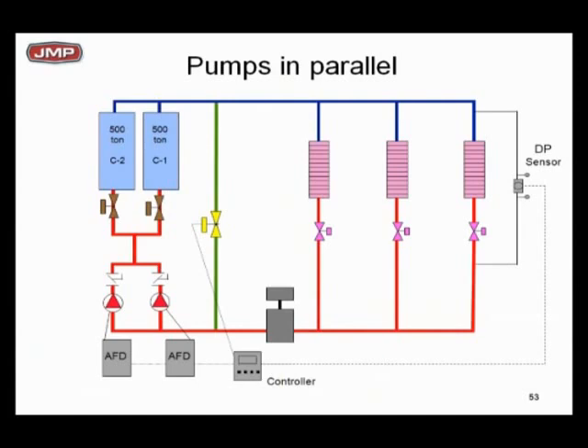Remember: if we put pressure drop in the common pipe, we force circulation in the secondary — that's all we're doing here. We get a little bypass, a green common pipe with a valve in it deliberately, throttling that valve to control the flow rates through the chillers and through the system — primary pump.